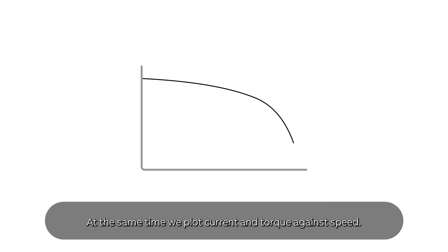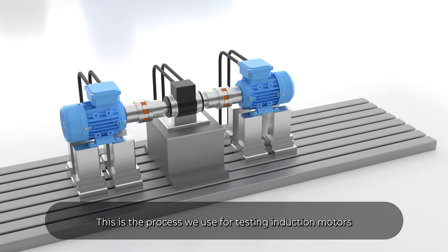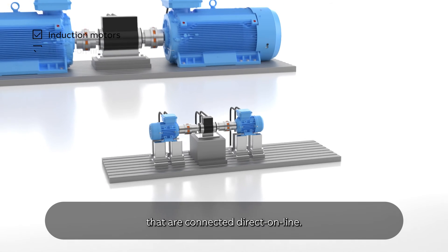At the same time we plot current and torque against speed. This enables us to find the starting current, starting torque and minimum and maximum torque. This is the process we use for testing induction motors that are connected direct-on-line.